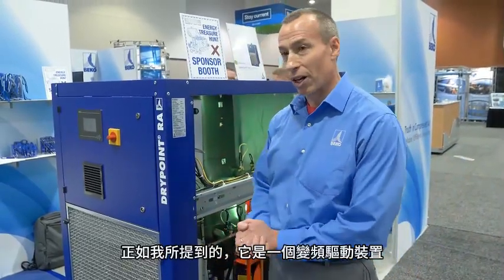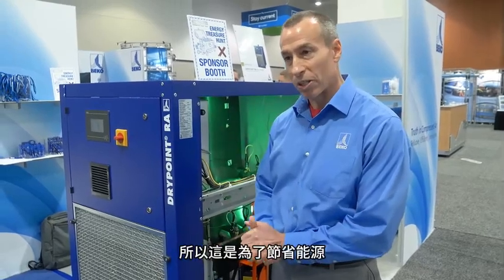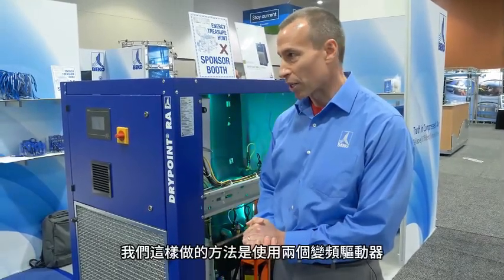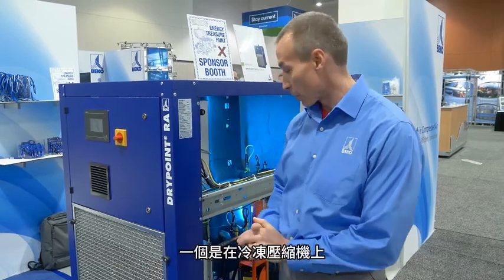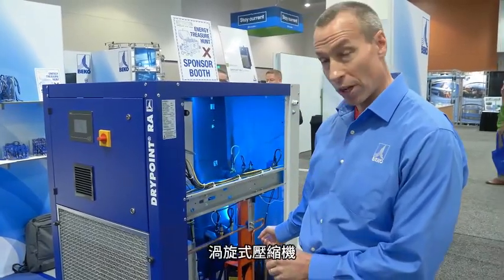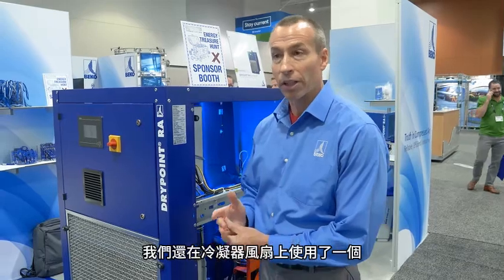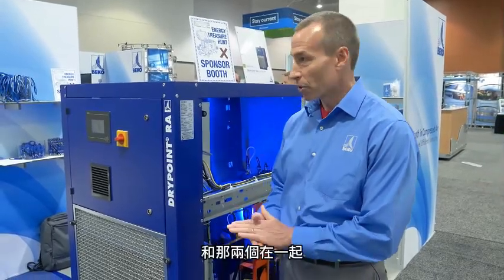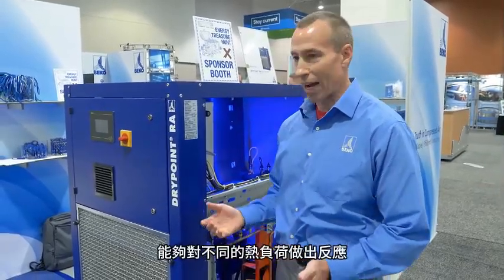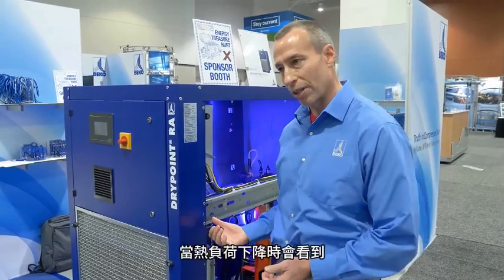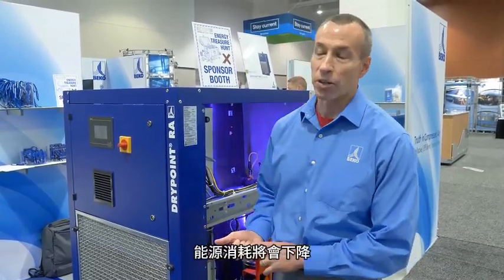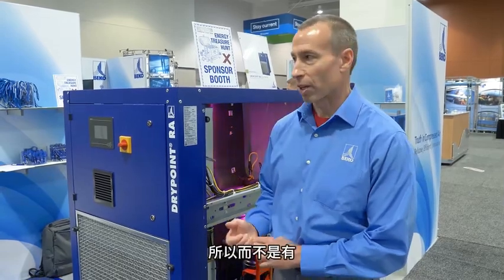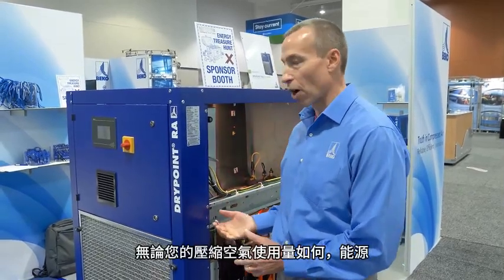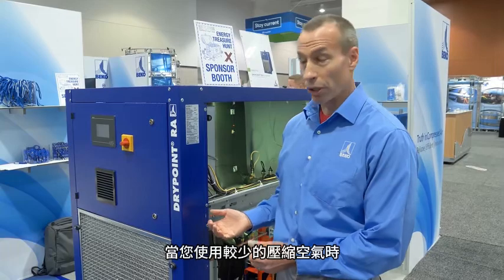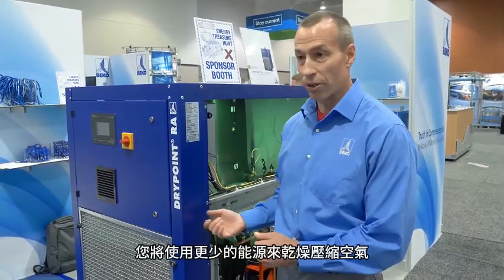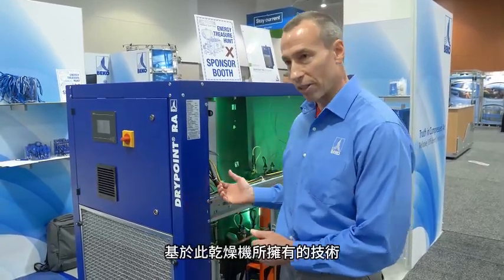As I mentioned, it is a variable speed drive unit, so it's meant to save energy. The way we do that is we use two variable speed drives. One is on the refrigeration compressor, which is a scroll type compressor. We also use one on the condenser fan, and those two together are able to basically react to the different heat load that the dryer will see, and when the heat load drops, energy consumption will drop. So instead of having this thing consume the same amount of energy regardless of your compressed air usage, when you use less compressed air, you will use less energy to dry that compressed air based on the technology this dryer has.